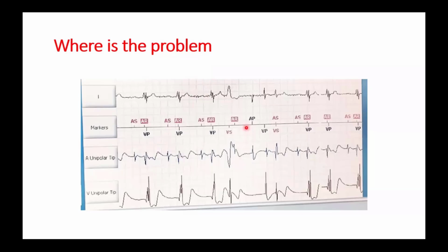Okay. So if we look, the first beat is an atrial electrogram, and then a ventricular electrogram, paced rhythm, and it is sensed in the atrial chamber. But because it is in the refractory period, it is atrial sensing in the refractory period. This is the far-field ventricle sensed in the atrial chamber and is marked as refractory.